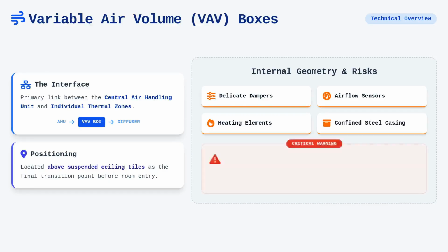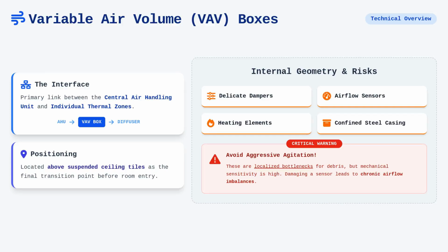When we perform system cleaning, these boxes act as localized bottlenecks where debris may accumulate, yet their mechanical sensitivity requires us to exercise significant restraint. Unlike main trunk lines, you cannot simply subject these components to aggressive agitation because damaging an internal sensor or vane can lead to chronic airflow imbalances throughout the entire zone.